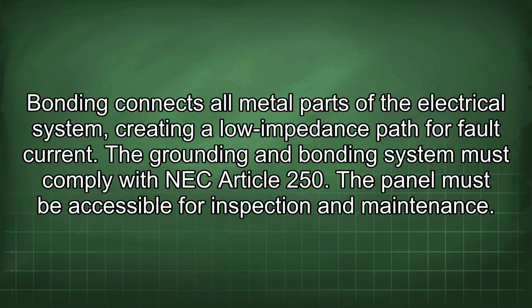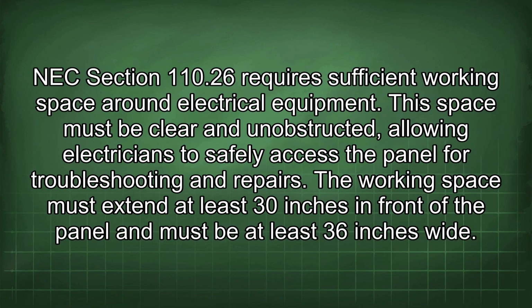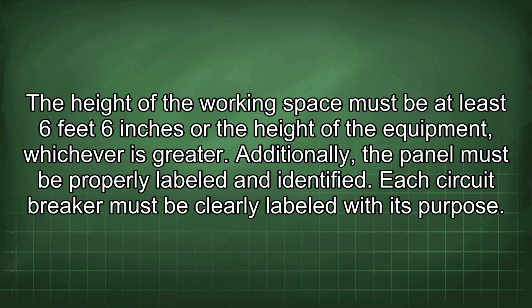The panel must be accessible for inspection and maintenance. NEC Section 110.26 requires sufficient working space around electrical equipment. This space must be clear and unobstructed, allowing electricians to safely access the panel for troubleshooting and repairs. The working space must extend at least 30 inches in front of the panel and must be at least 36 inches wide. The height of the working space must be at least 6 feet 6 inches, or the height of the equipment, whichever is greater.